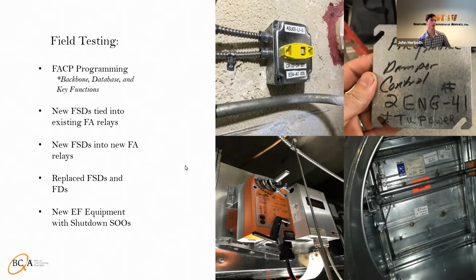Now let's keep rolling. And then we also had some problems with some EF equipment shutting down and working correctly. So smoke evacuation ends up being another critical part of the commissioning side. And the functional test, you can't replicate it. You have to go through and be able to shut it down. And so one thing you tend to lean on is using the fire alarm contractor to set up programmed buttons to test specific relays to trigger it, so that you don't have to go out in the field and smoke a head or smoke a duct detector. Especially in an older hospital that's had many remodels, the programming ends up being, you try to find what's connected to what relay, and the documentation just isn't there for you to make sure and validate that you're not going to impact something else.